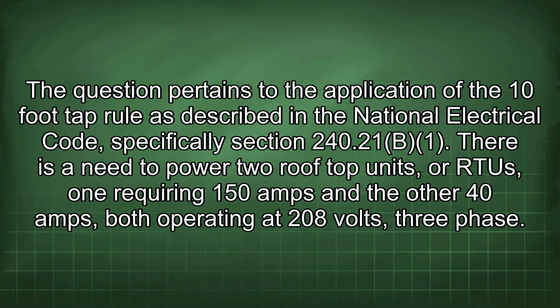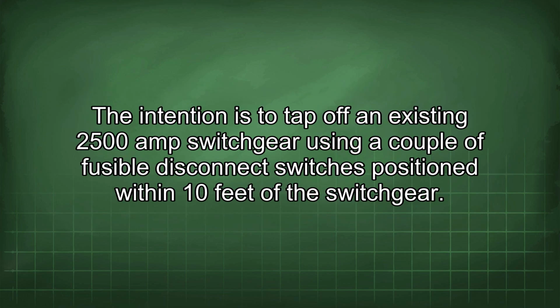The question pertains to the application of the 10-foot tap rule as described in the National Electrical Code, specifically Section 240.21(B). There is a need to power two rooftop units, or RTUs, one requiring 150 amps and the other 40 amps, both operating at 208 volts, three-phase. The intention is to tap off an existing 2500 amp switchgear using a couple of fusible disconnect switches positioned within 10 feet of the switchgear.